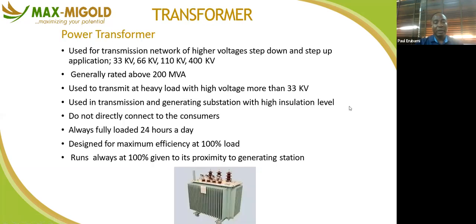So we have the transformer, as we mentioned in our first or two slides. It modifies voltage from a higher voltage to a lower voltage, and from a lower voltage to a higher voltage. We have the primary side and the secondary side. If you want to step up your voltage, the number of turns in the secondary must be higher than the number of turns in the primary. Like most transformers, they have 400 volts on the primary, the input side, while the output side is about 11,000 volts, that's 11 kV. If you want to step down from 11 kV to 400 volts, it's the same thing. It's the turn ratio that differs.